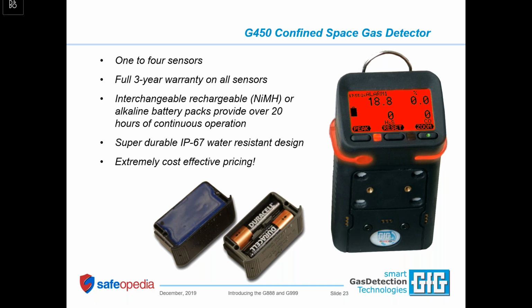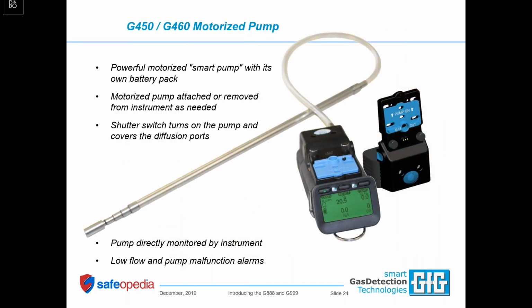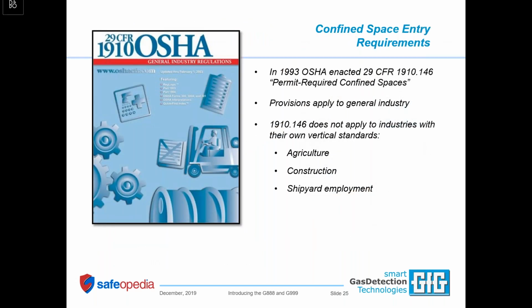One of the issues that makes it so attractive is having interchangeable battery packs that allow you to switch over to alkaline batteries or use alkaline batteries 100% of the time, and you never have to worry about charging or doing anything to have the instrument ready to rock and roll. With the 450 and 460, we also have a separately powered attachable pump. That is a unique capability. If you want to have the pump, you attach the pump. If you don't want the pump, you can remove the pump, or you can leave the pump attached and still use the instrument in diffusion mode. It's very flexible, it's unique, and it's a pretty nice option to have.